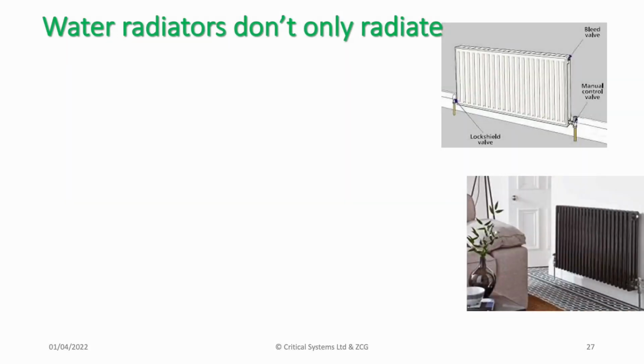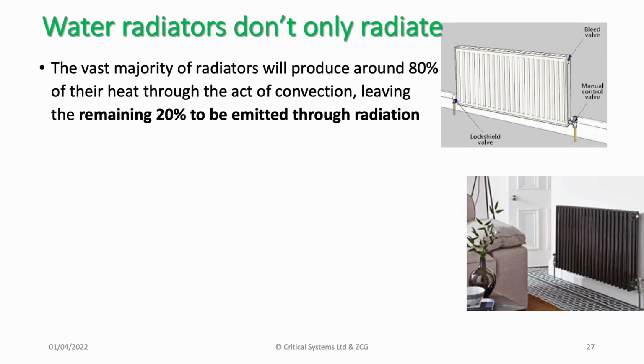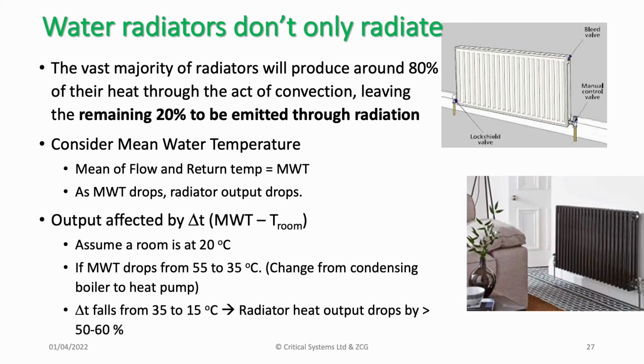Now again, from my last talk, remember I said that water radiators don't only radiate. Actually, 80% of the heat released into a space from a radiator comes from convection, with 20% emitted through radiation. When evaluating the output from a radiator, we need to consider the mean water temperature between flow and return, and as that mean water temperature drops, radiator output drops.